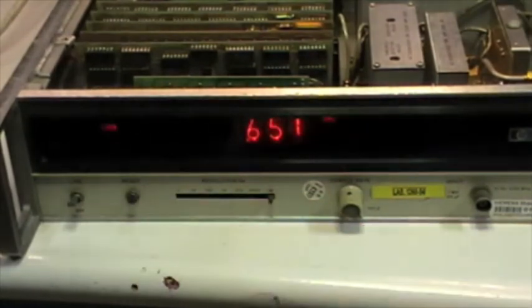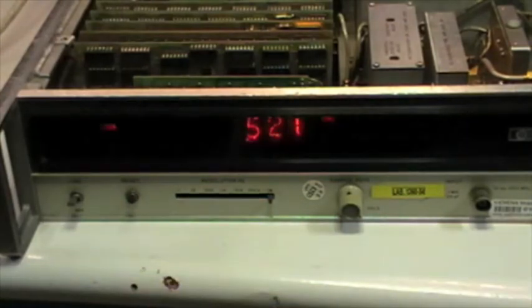Yeah, it's locked, but it's not counting exactly. So 10 millivolt. Let's reset, and it's going more close. So the unit is counting, so it's running, but it's not precise. So I will attempt the calibration to see if it fixes the problem. Of course, clean all the contacts and back to the camera.